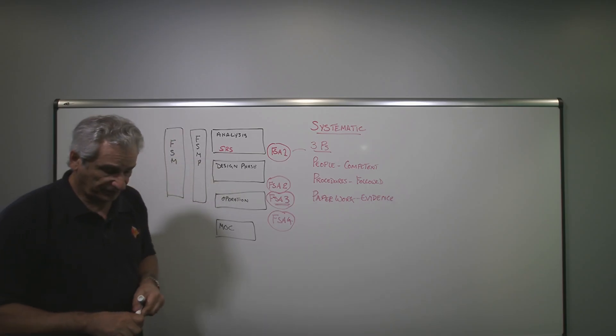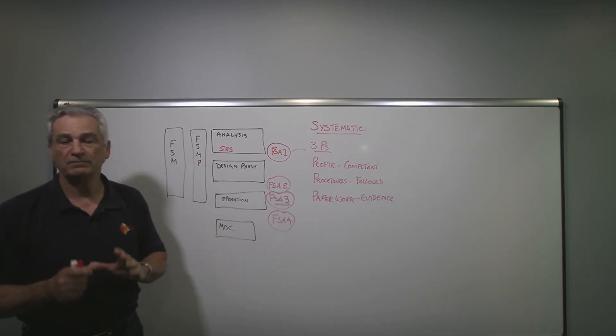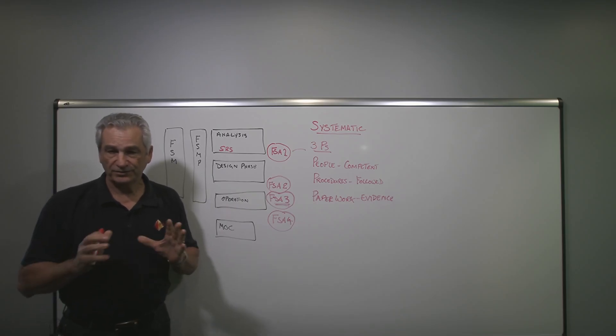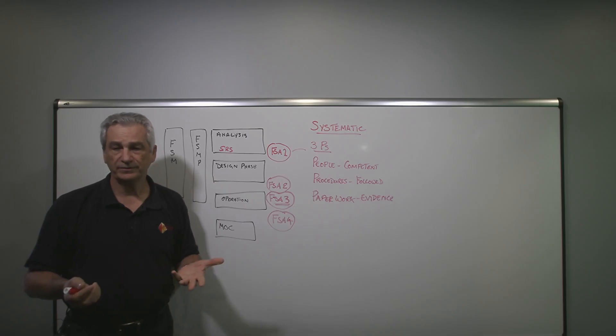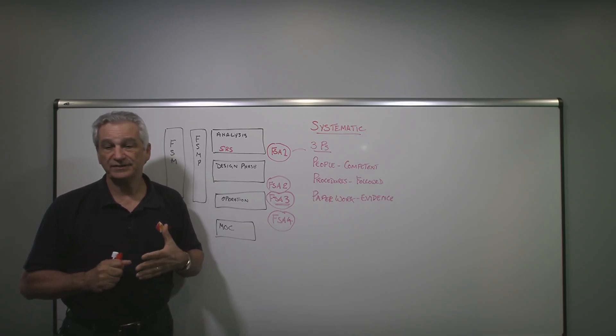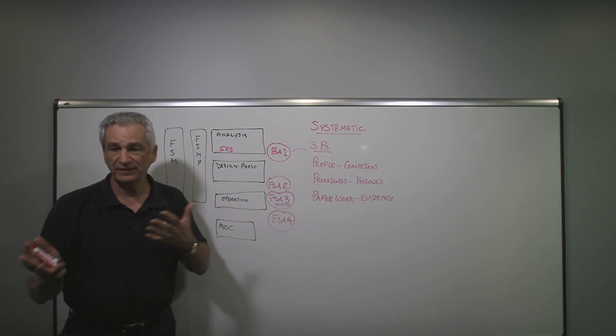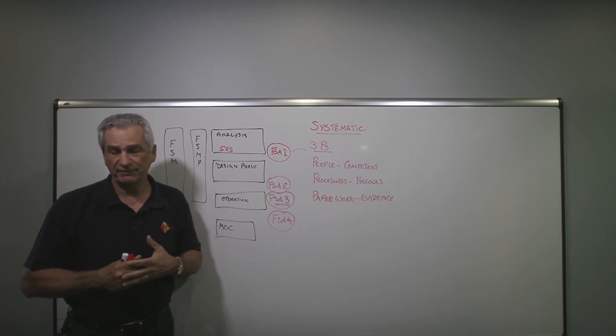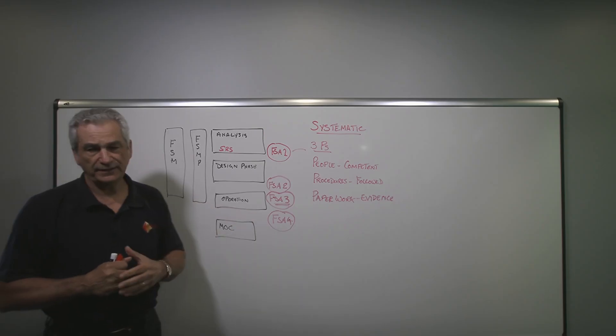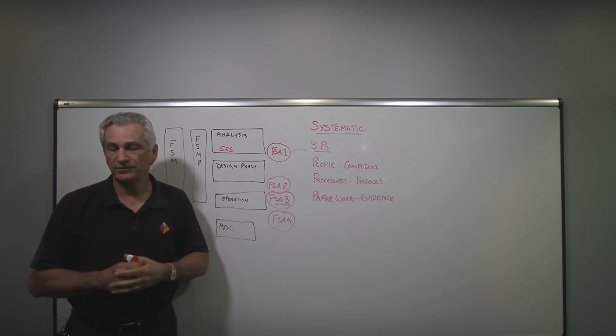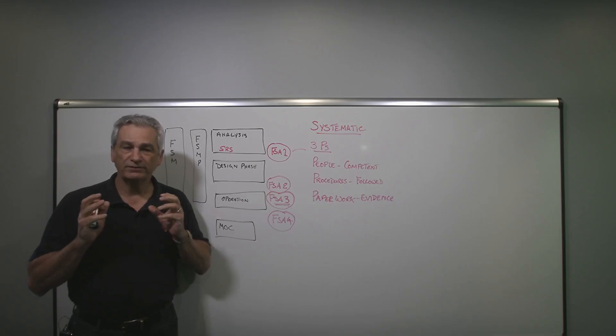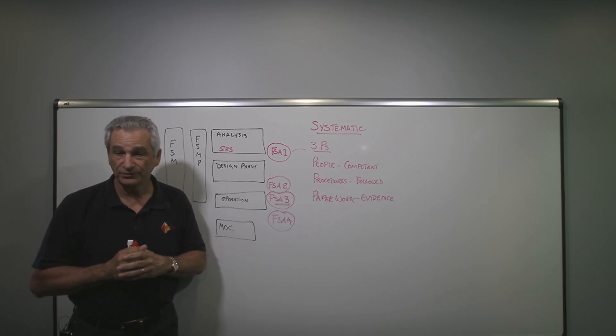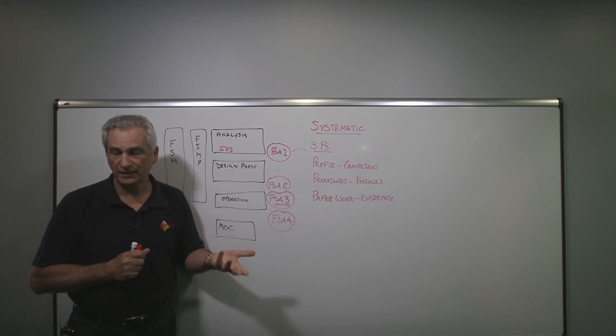After some period of time in operation, we should be doing an FSA-4. This is the other mandatory requirement. The purpose of this is because the IEC 61511 is a performance-based standard, not a prescriptive standard. Some of the older standards were prescriptive. What do we mean by prescriptive? Prescriptive is where it says this is what you have to do, and then it tells you how you have to do it. There's no leeway, no flexibility. It's got to be done. NFPA 85, double block and bleed.